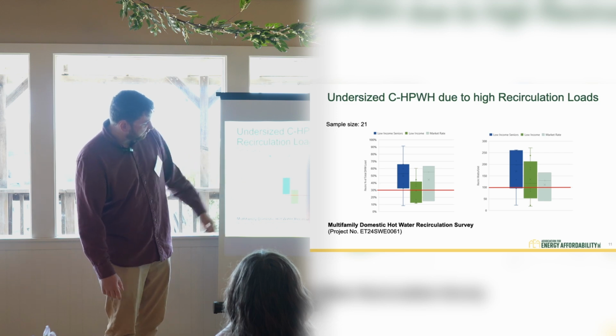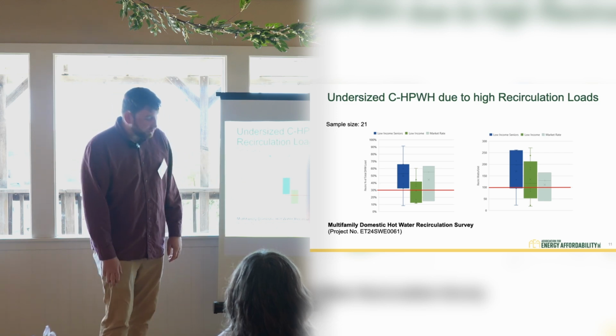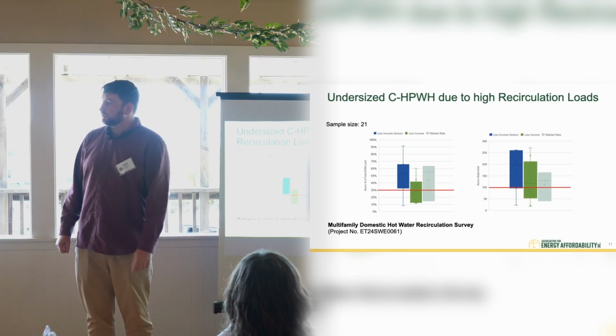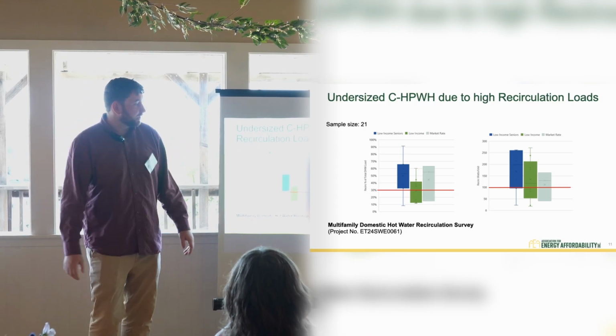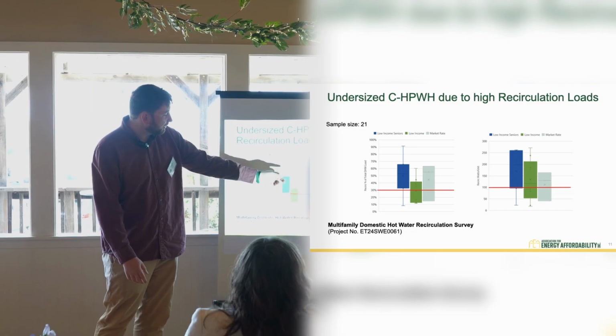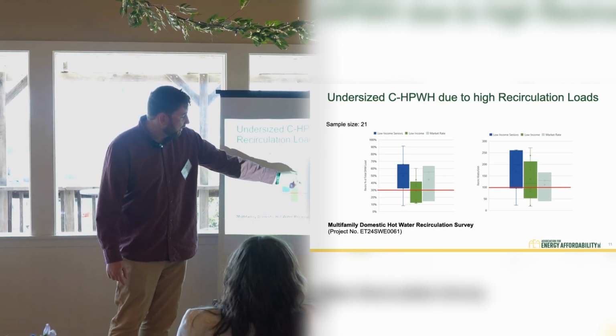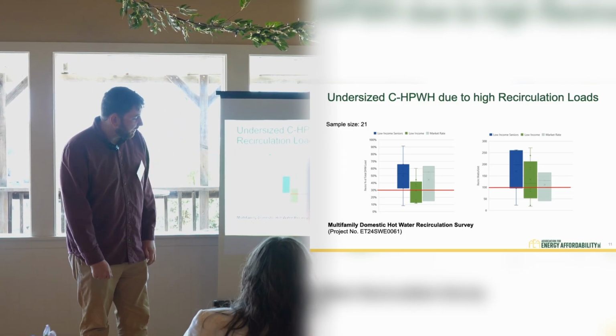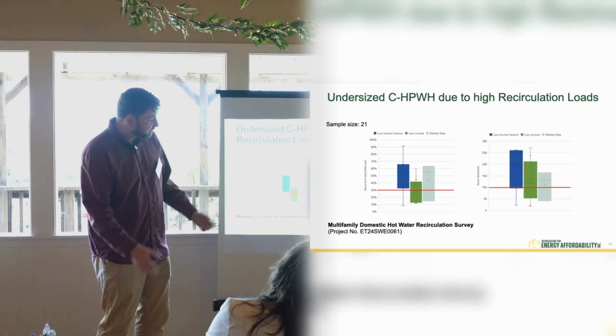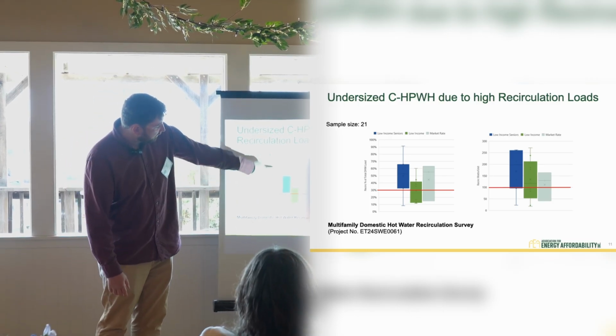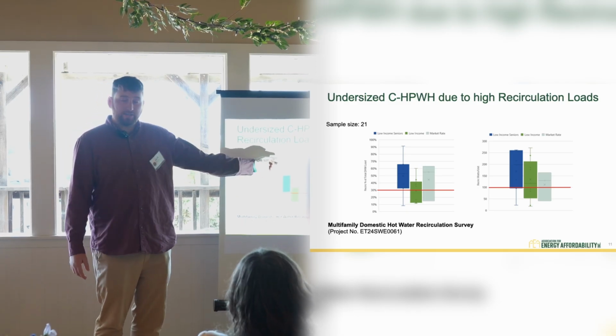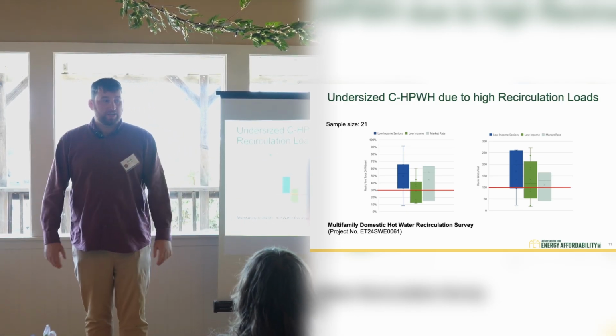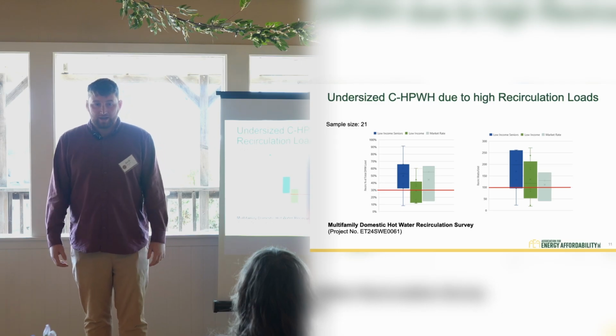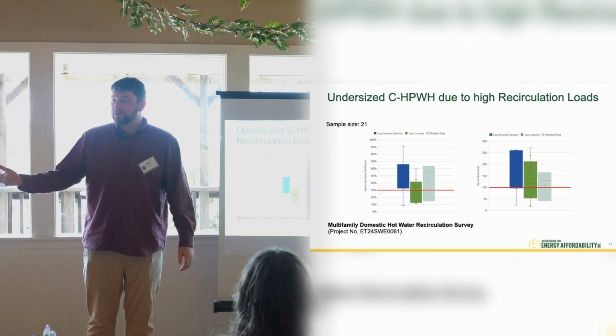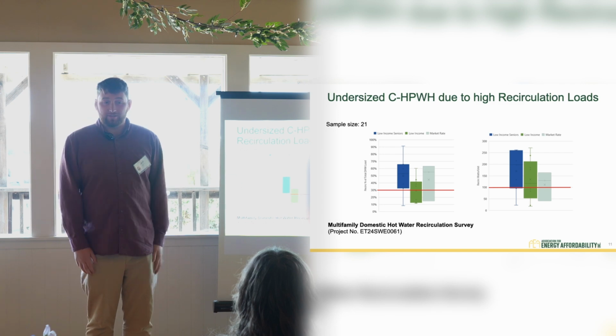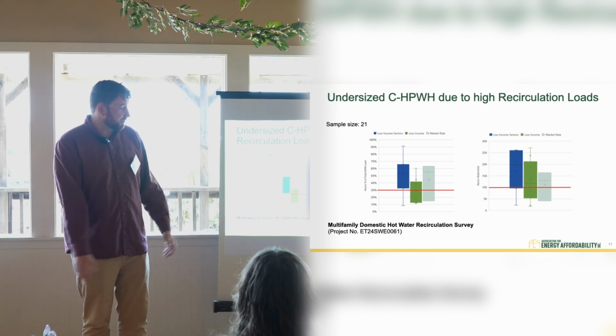More complex, you might have multiple loops going back and going out and coming back. This graph on the left is the percentage of load that is recirculation or distribution losses in domestic hot water buildings. Sample size is 21. Blue is low income, seniors, green is low income, and this teal color is market rate. We don't have that much market rate data because we mostly do affordable housing, but you can see the low income seniors. We have projects where 92% of the load is reheating water coming back to the distribution system. How do you size a heat pump water heater for that, where you have a swing tank that is in charge of reheating that load? It's almost impossible. You're going to have electric resistance water heating.